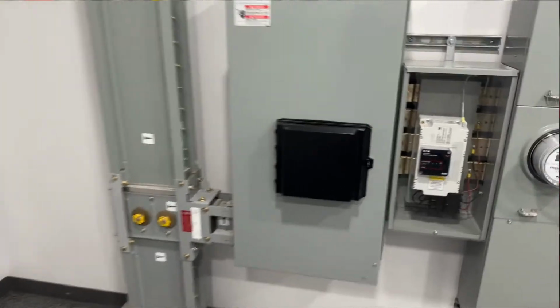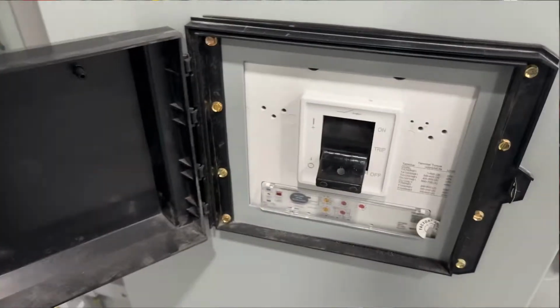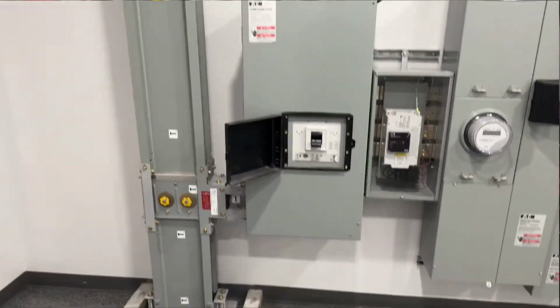So there's another busway. What's that? Is that a disconnect? Or is that a main breaker? That's a main breaker. That's a nice. So okay, I just turned that camera off, John. So there are a lot of ways for disconnects. There are a lot of uses for disconnects. What's that there? That's an EV charge busway, EV charger. So we have switches in high locations, switches in low locations, switches outdoors, switches indoors. Multiple pole snap switches. Let's take a look at that.